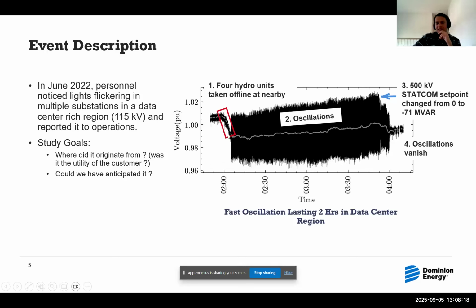Back in June 2022, we removed some hydro units close to a data center rich region. It's mainly a 115 kV network, so it's not a tightly coupled or strong grid in that part of the system. As soon as we took the hydro units offline, we started seeing oscillations around 14 to 15 hertz, and they lasted for a full 2 hours. Then the system changed, and the oscillation suddenly vanished.